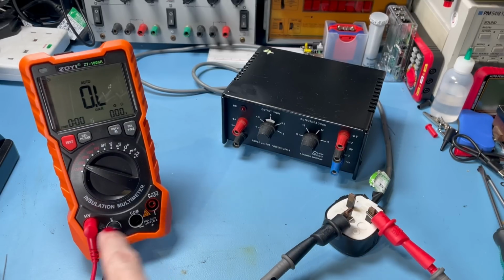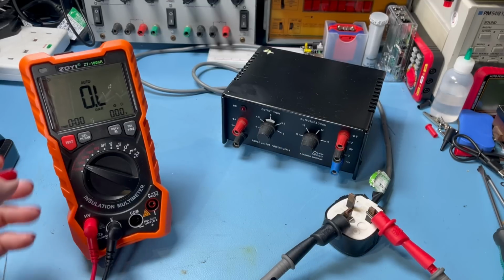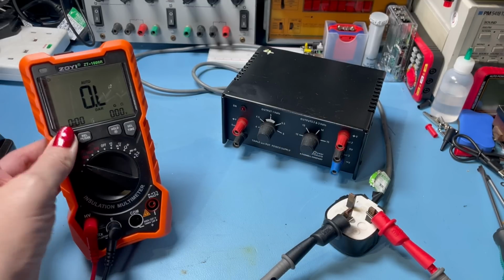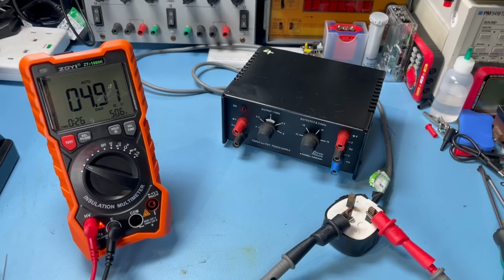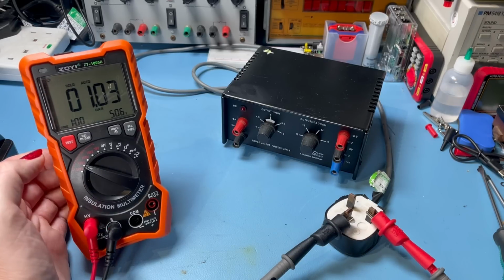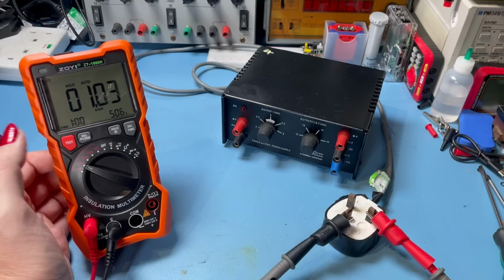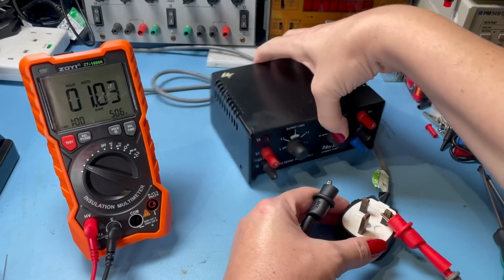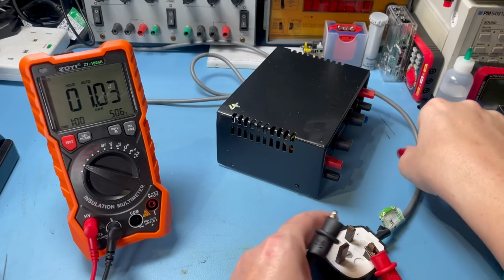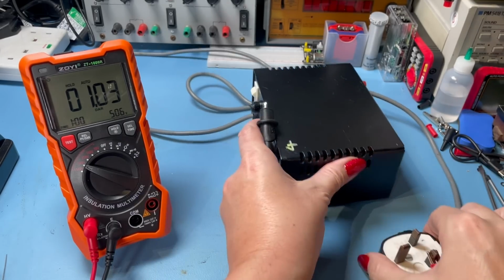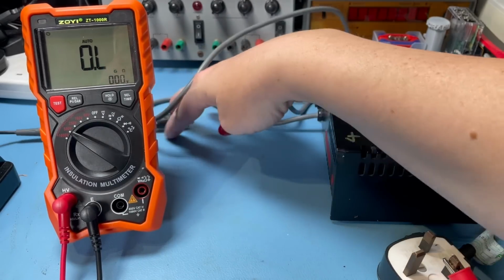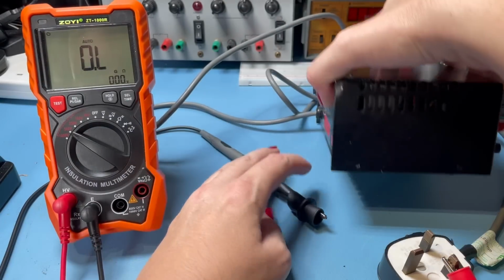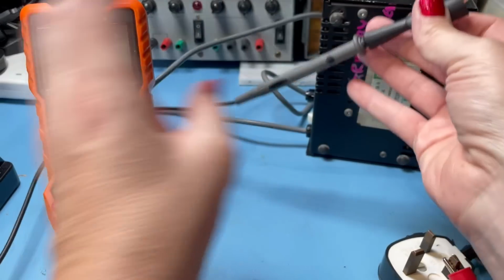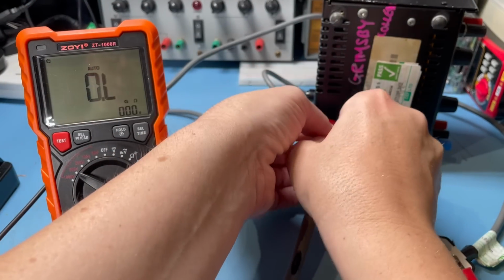Now, when your red triangle is on, don't be touching that. That's all I will say. Let's test. There we go, so we hit 5 gig ohms of resistance on there and a DAR of 1.03. Now, one final test I want to do, which is more reminiscent of a portable appliance test, is I'm going to test the live there to the metal casing or chassis of the device under test. Nice exposed screws on the bottom, that's always a good place to go.